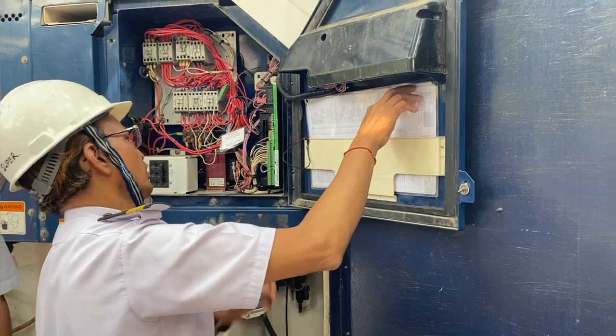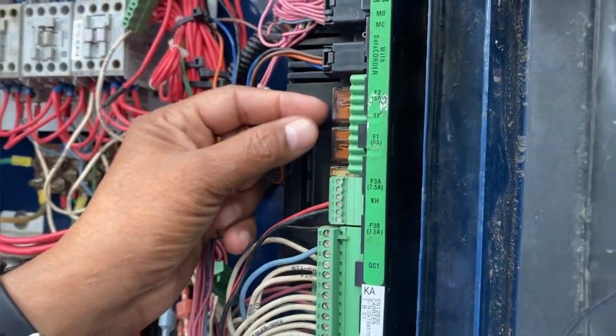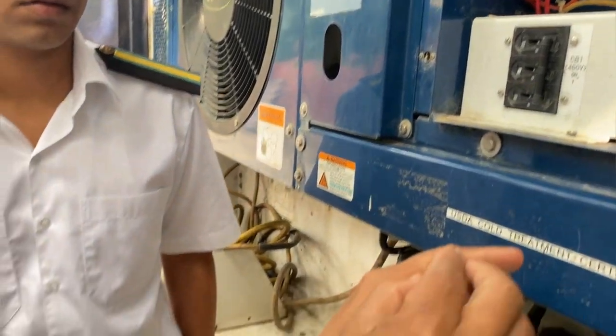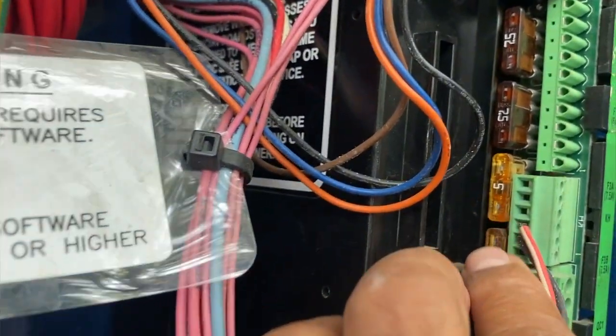The diagram is kept in a pocket inside the panel. You also have the controller and different components. Here are the fuses. If you want to check, you can remove the fuse. How much is this fuse? Not 20 — it's 7.5 amps. So there are two fuses: the correct one is 7.5 amps. Another one is also 7.5. And this one? 5 amps. You can see: this is 5 amps, and another one is also 5 amps.